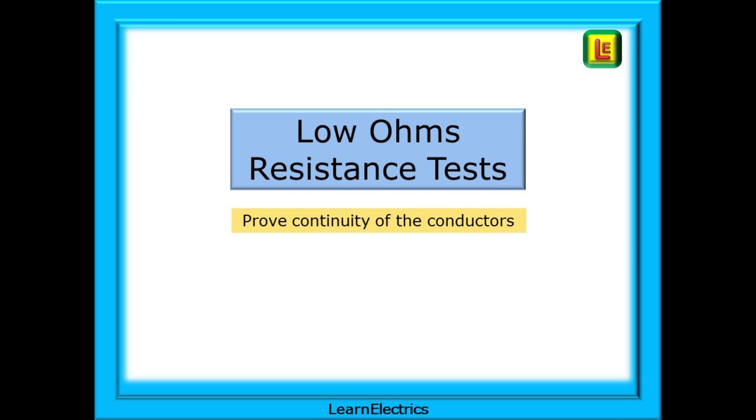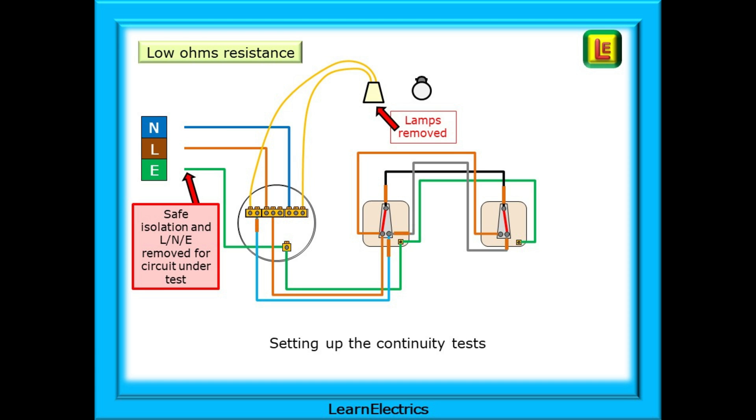Our first tests should be the low ohms resistance tests. This will prove the continuity of the circuit conductors, an important first step. For this radial lighting circuit these tests will give us the R1 plus R2 readings that can be entered onto the test certificate and are also used for determining what ZS should be. These are dead tests so carry out safe isolation as a first step. All lamps and transformers etc should be removed from circuit so that we are left with just the wires on their own. Anything left in circuit may give incorrect readings.